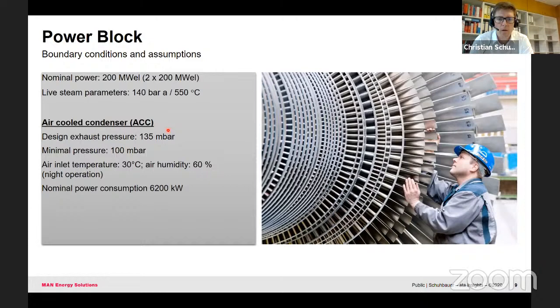Quite important is, of course, also the air-cooled condenser. The design exhaust pressure for our component is 135 millibar, so a minimum of 100 millibar would be possible for operation. The design case was night operation, meaning 30 degrees C ambient temperature and an air humidity of 60%.